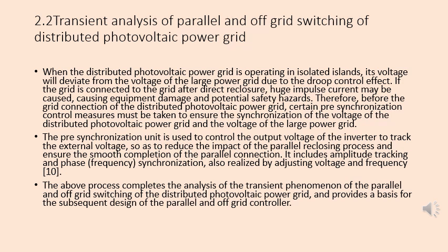Therefore, before the grid connection of the distributed photovoltaic power grid, certain pre-synchronization control measures must be taken to ensure the synchronization of the voltage of the distributed photovoltaic power grid and the voltage of the large power grid. The pre-synchronization unit is used to control the output voltage of the inverter to track the external voltage, so as to reduce the impact of the parallel reclosing process and ensure the smooth completion of the parallel connection.